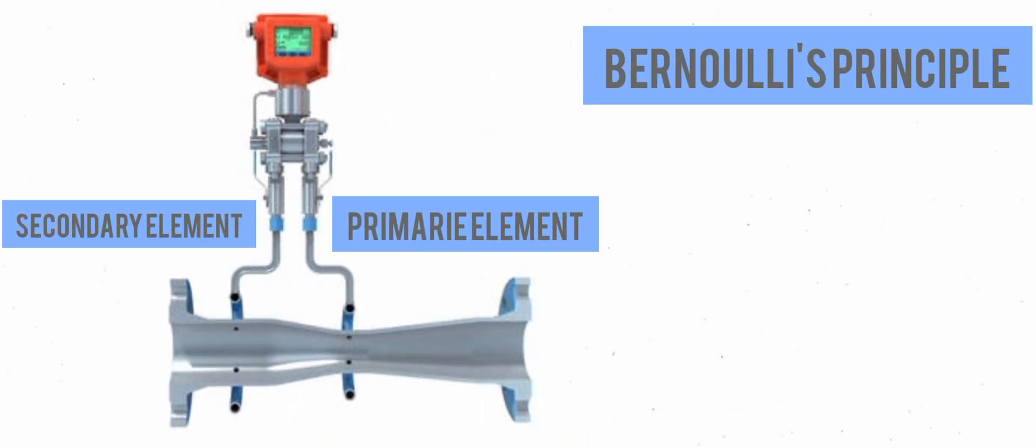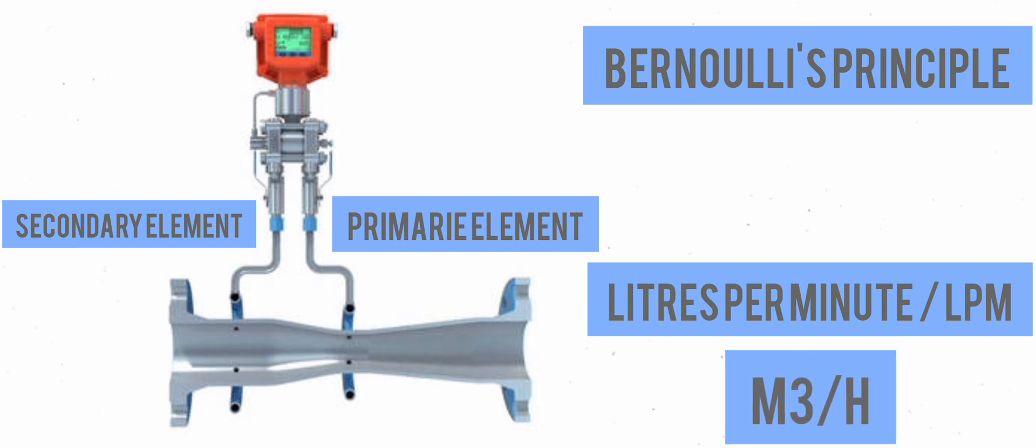By using Bernoulli's law, which states that the pressure drop across the constriction is proportional to the square of the flow rate, the differential pressure is then converted into units of flow. These units of flow can be liter per minute or cubic meters per hour.